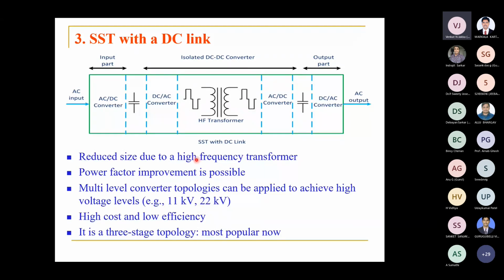The key merits of this kind of structure are reduced size due to the high frequency transformer, and power factor improvement is possible because you are adding storage capacitors, so they can inject and take reactive power to support compensation and additional power factor adjustment.